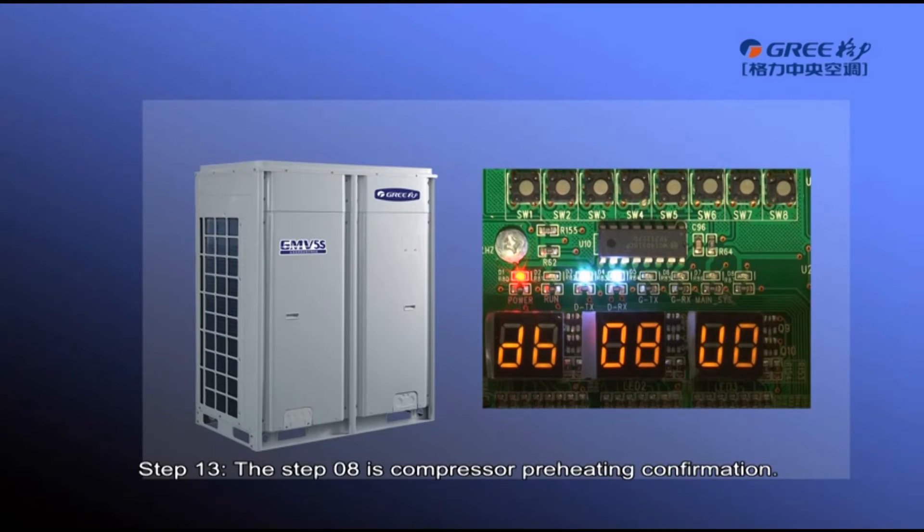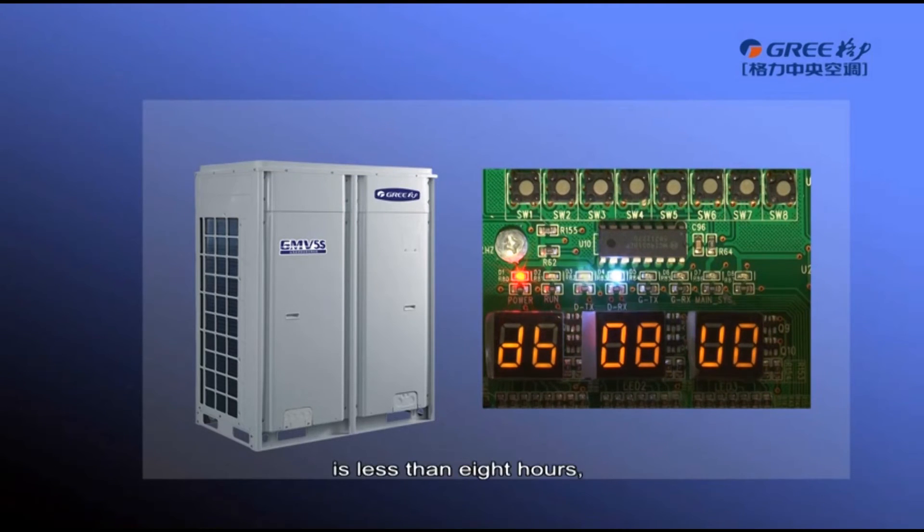Step 13, Step 08 is compressor preheating confirmation. If it is detected that the compressor preheating period is less than 8 hours, error code U0 will be displayed. Therefore, please preheat the compressor in advance. If it is detected that the compressor preheating period is more than 8 hours, the unit will enter step 9 automatically.